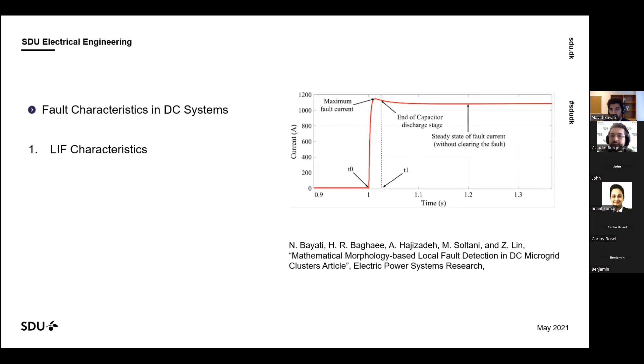And when we talk about high impedance faults, it is something like this. Because the fault impedance is too high, we have some oscillation. It's something like an arc, and the magnitude of this oscillation is not too high, so it's really hard to detect them. But if these oscillations remain in the system, they can cause some heating, and sometimes we have some firing in the system.